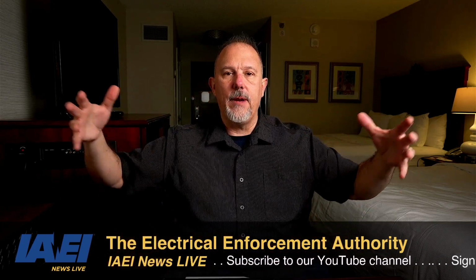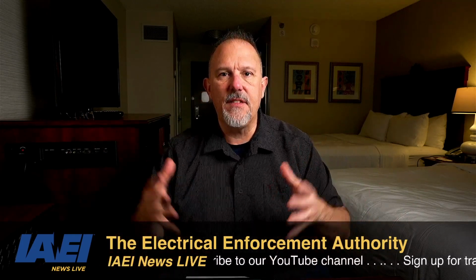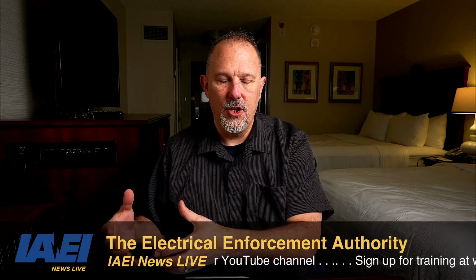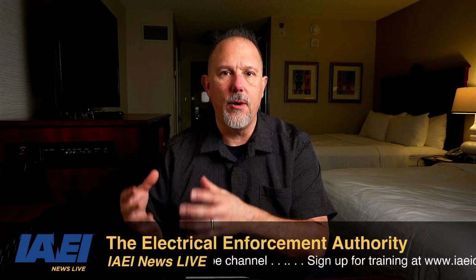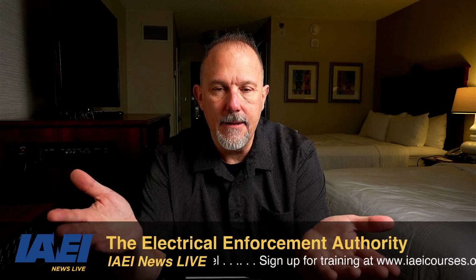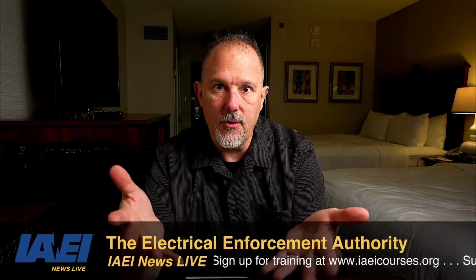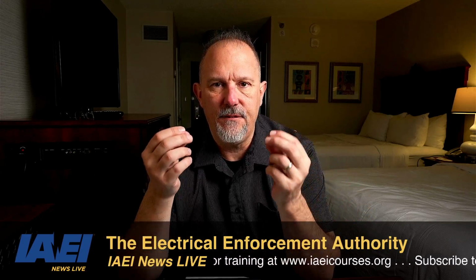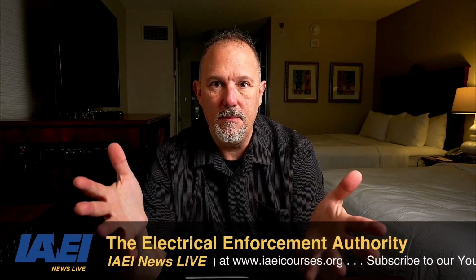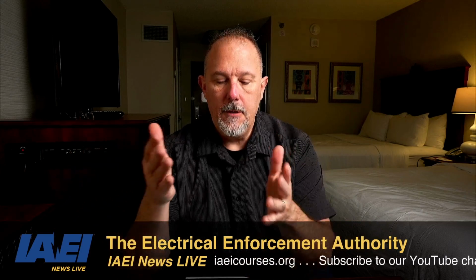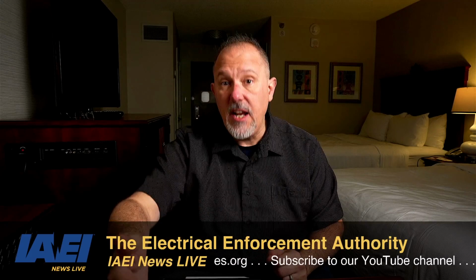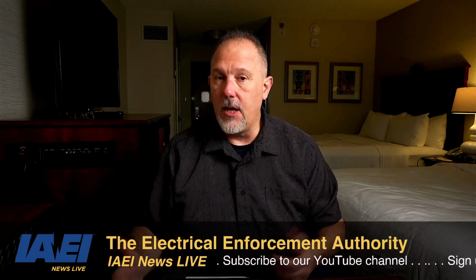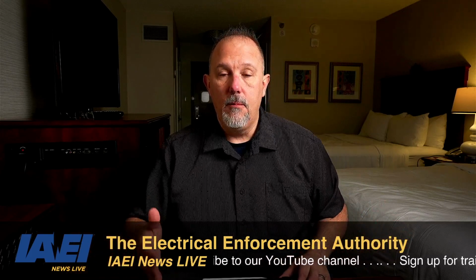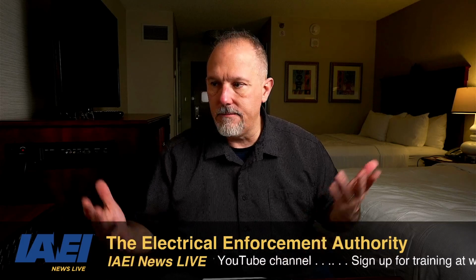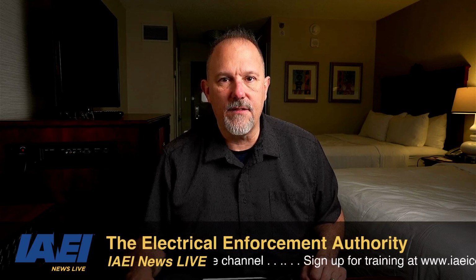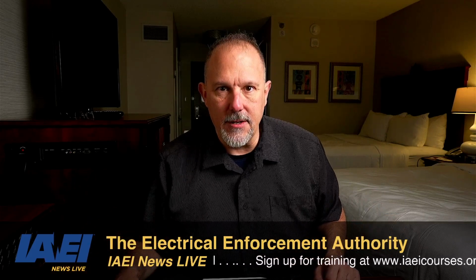So the bigger the generators get, the bigger the motors get, you'll have specific relays to protect your investment. You want to determine when that big piece of equipment is going to fault earlier. You'll put temperature sensors, RTDs, inside of the windings of motors and transformers and generators, because you want more information to detect failures early, because you may be able to rewind the motor and fix it or fix the generator. So there are protection levels that you will spend money on, or not, maybe not you, maybe the owner and the designer may say, look, we're going to put more protection on this generator because you spent a couple million on it, and we can rewind it for a few hundred thousand as opposed to replace it for another couple million. You know what I'm saying?